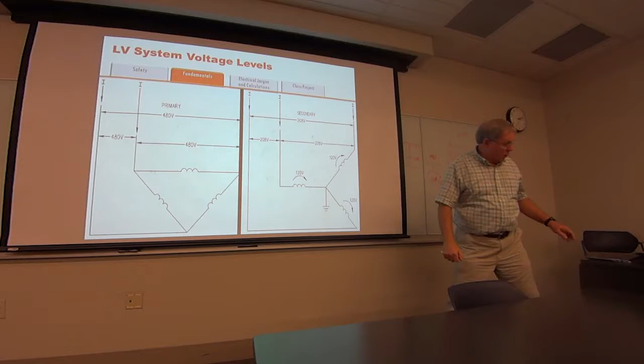Big dry type transformer. That's 2.5 MVA. Primary compartment goes to the transformer. It's got three great big old cores in here. And then this is a secondary breaker. It's a 4,000 amp breaker. And you can see the cables coming out. This is the cable going in right here, a little cable about that big. And these are the cables coming out. So you can see what happens when you drop the voltage and raise the current.